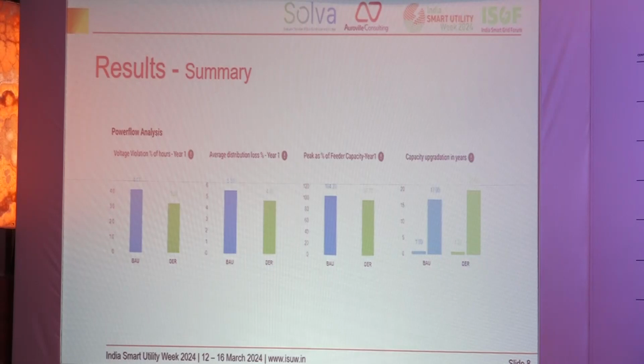We propose capacity upgradation by considering 5 instances in a year where peak capacity has been violated above 90%, and this threshold value can be set in the tool. If we cross 5 violations of the feeder or infrastructure capacity, we propose an upgradation. For example, in this case, the BAU scenario requires upgradation in year 1 and again in year 17 of a 25-year analysis period, while integrating a DER on this network has deferred the second upgradation by 3 years.